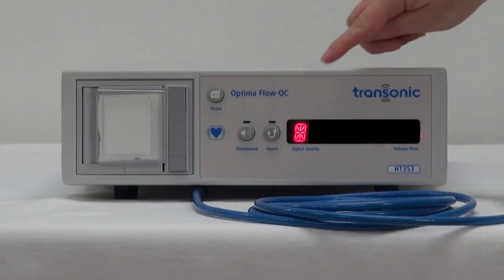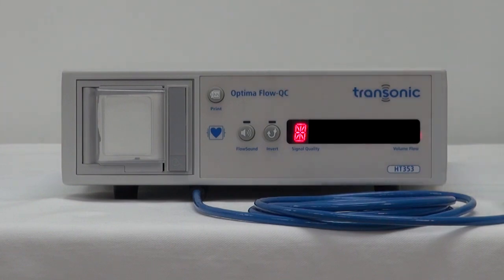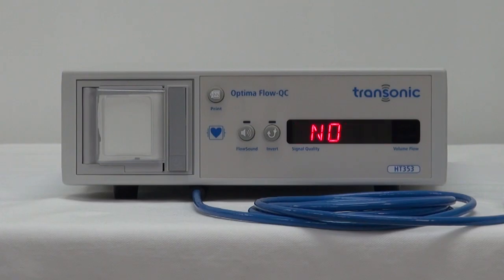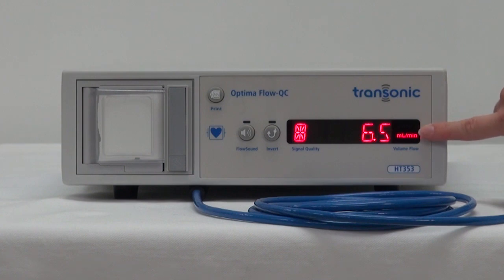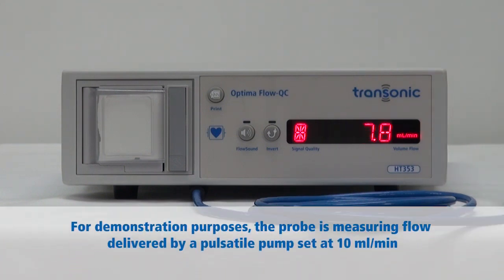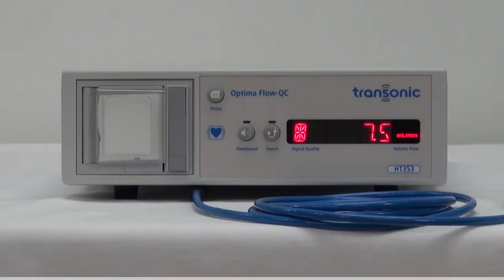The bucket indicates the signal quality of the flow probe. The fuller the bucket, the better the signal. If the received signal is too low, reading less than 15%, the meter will revert to the no signal acoustic error condition. Check to make sure there is no air in the flow probe window, which could be blocking the signal. Once acoustic coupling has been achieved, the volume flow is displayed on the front of the meter. On keyed meters, the 4-hour timer will start.